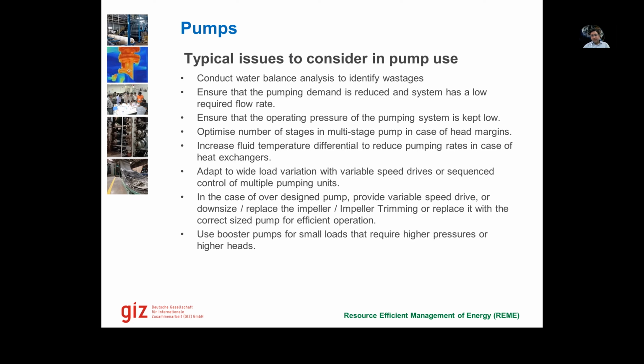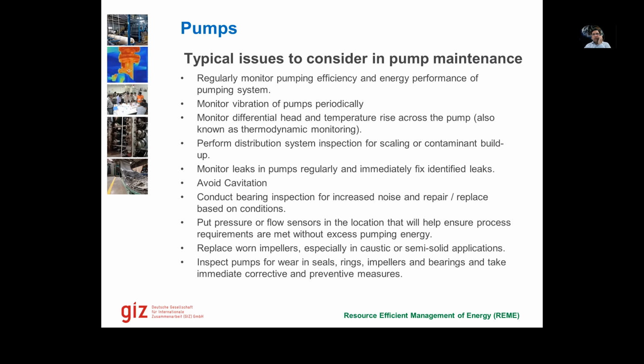If we need high pressure in some areas, we could use booster pumps in those areas rather than increasing the pressure of the whole system. And then maintenance is something that we also need to take care of. Monitor the temperature of the pumps, vibration, noise, and monitor the knocking in the piping system, for example, and see how it is performing and in which areas we are getting more knocking. If there is air trapping in the pipes, do we have proper air vents installed or not? And if there are any leakages.